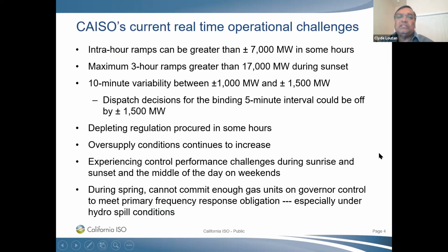Now, what are some of the challenges that the ISO faces currently? Every system is different. If you integrate wind, it's a lot different than if you integrate solar. And it also depends on the resource makeup of your existing resources. But currently, at the California ISO, we are seeing some huge intra-hour ramps, about plus or minus 7,000 megawatts in an hour. And that's a lot of megawatts to move in 1 hour.